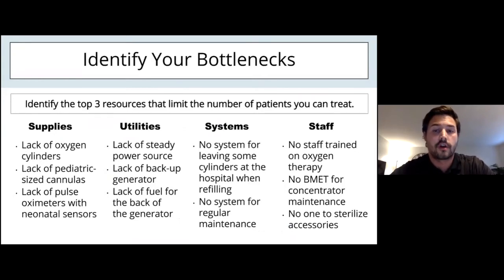So when we first start, normally the number of oxygen cylinders or concentrators limits the number of patients that can be treated. That's typically the case. We see that across the board. That's always the first thing people say, we don't have enough oxygen. However, as we increase the volume of available medical oxygen, we find sometimes we can't use all the oxygen because we're missing other key supplies or systems.